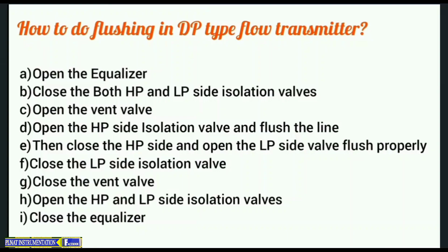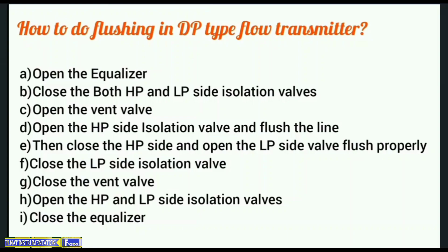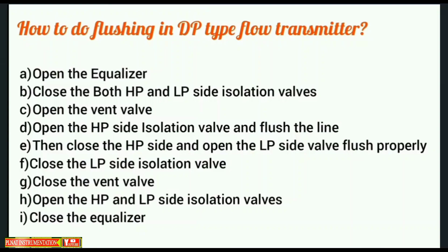How to do flushing in a DP type flow transmitter. A. Open the equalizer. B. Close both the high pressure and low pressure isolation valves. C. Open the vent valve. D. Open the high pressure side isolation valve and flush the line. E. Then close the high pressure side and open the low pressure side valve and flush properly. F. Close the low pressure side isolation valve. G. Close the vent valve. H. Open the high pressure and low pressure side isolation valves. I. Close the equalizer.